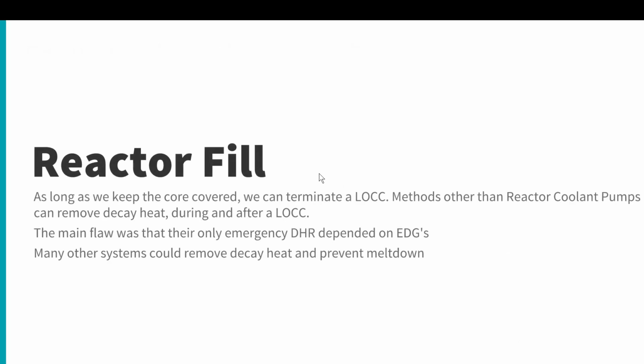So basically anything that sort of goes along with our traditional concepts of reactor fill that then keeps the core covered and then removes the decay heat would have been able to work to prevent this disaster. But the problem was that they just had emergency decay heat removal that was from the diesel generators with reactor coolant pumps. So of course many other systems could have removed the decay heat, but ultimately it was a design flaw that they didn't have any redundancy.